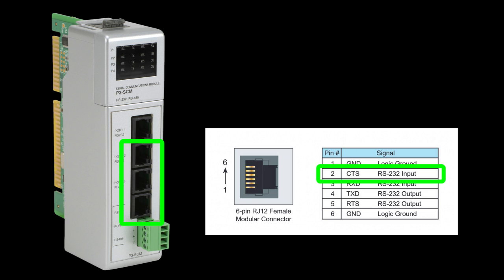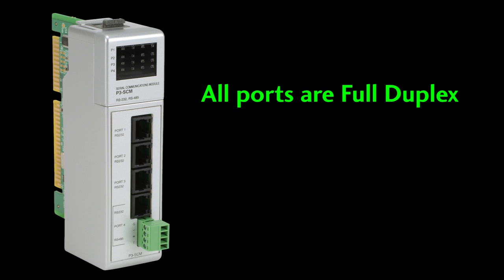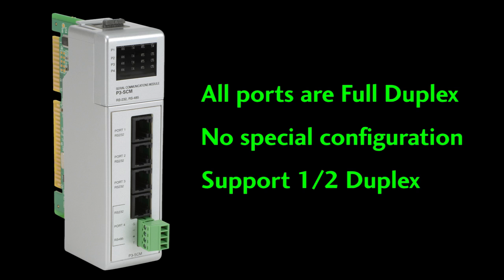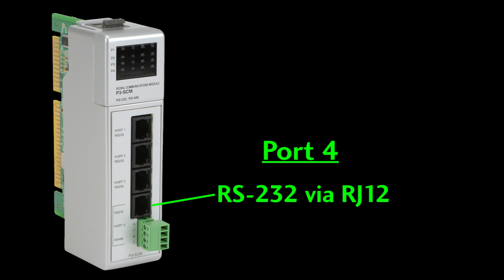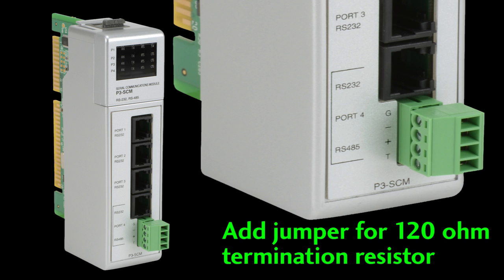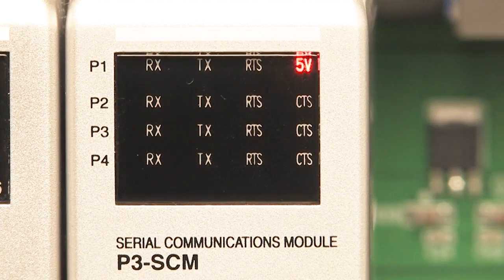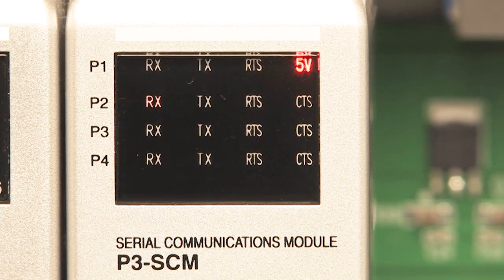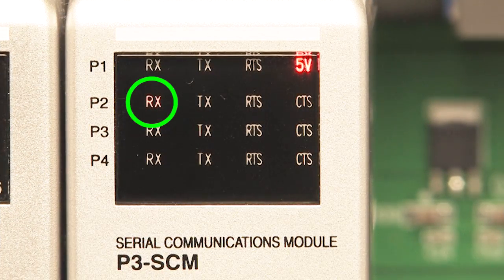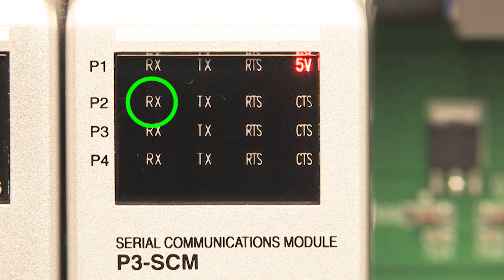Ports 2, 3 and 4 do have the CTS pin for handshaking if you want it. All of these serial ports are full duplex ASCII ports that require no special configuration and they support half duplex too. Port 4 can be used as an RS-232 or RS-485 port. And if you are using RS-485 you can add a termination resistor simply by jumping T to plus right on the front panel terminal block. The LEDs on the front panel are great for debugging issues. You can see at a glance if there is activity on any of the lines.